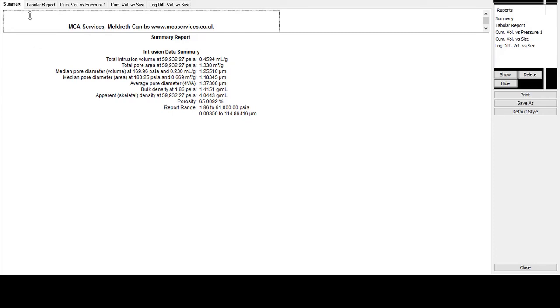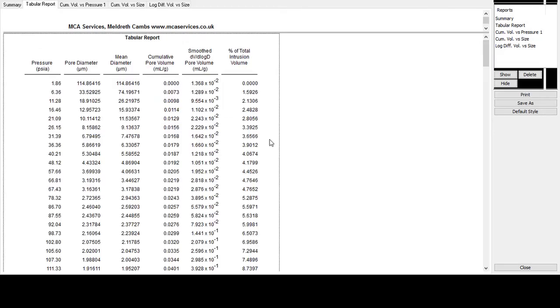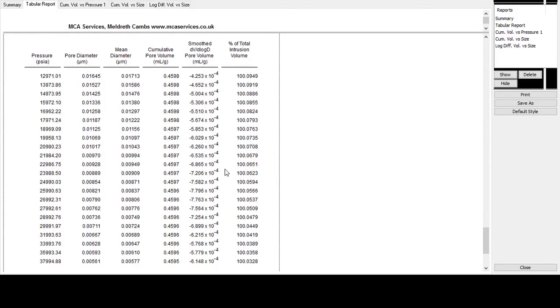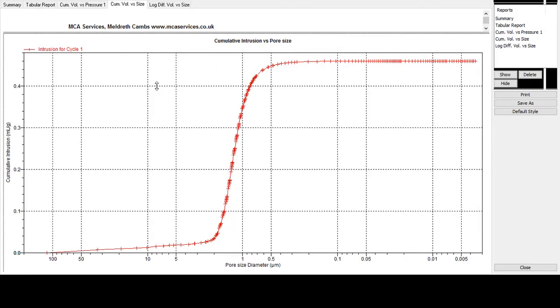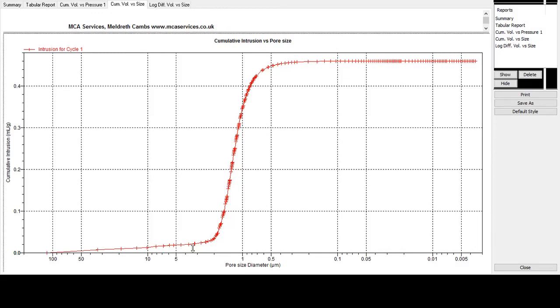We can see the raw data in tabular form. Now that goes on probably for this sample about 12 to 15 pages. The plot that we saw being generated on screen live, as it were, is the cumulative intrusion against pressure curve. So pressure on the x-axis down here. But now the intrusion volume on the y-axis is now showing as per unit mass of sample. Through application of Washburn's equation, we can transform that to a plot of pore size against intrusion volume. So pore volume again on the y-axis here, but now the x-axis is showing the pore size diameter in microns. And the final plot is the log differential plot of that curve.